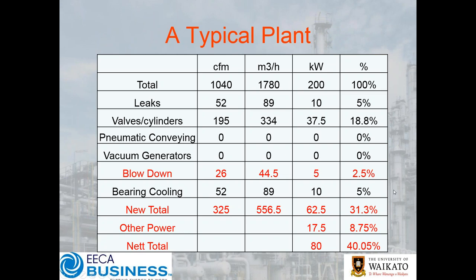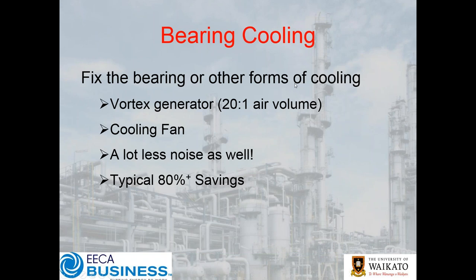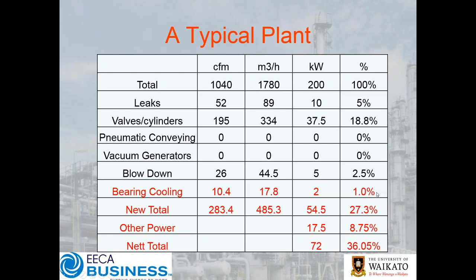Updating our typical plant: with blowers we've taken a 75% reduction on blowdown, dropping it to 2.5%. Our total numbers are really starting to drop, and even allowing for the extra ancillary equipment added, we're now down to 40% of our original power consumption. For bearing cooling, using a vortex generator or cooling fan gives typical power savings of around 80%, with a lot less noise. Updating our chart, we're now down to 27% of our original air use, and even allowing for the extra vacuum and blowers, we're still only at 36% of where we started — we've gone from 200 kilowatts down to 72.